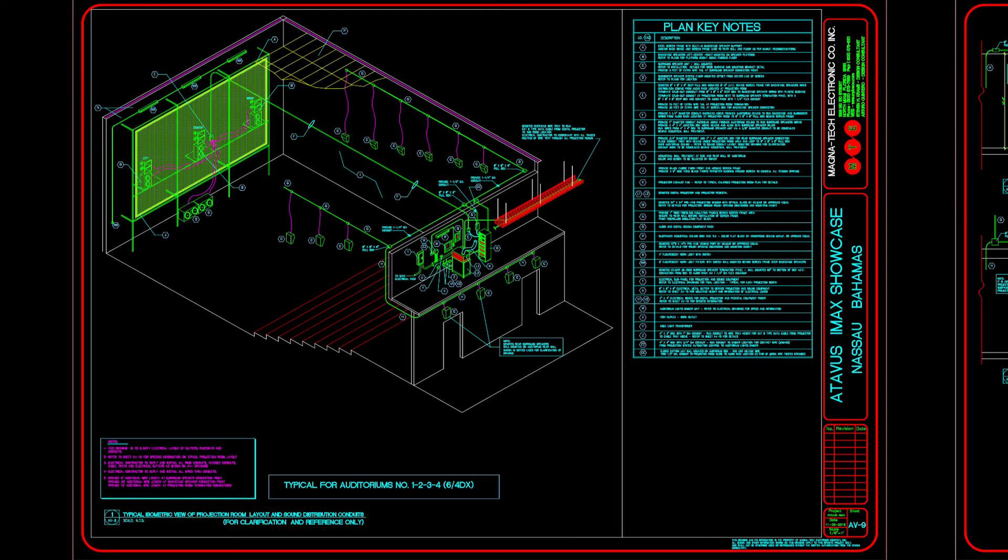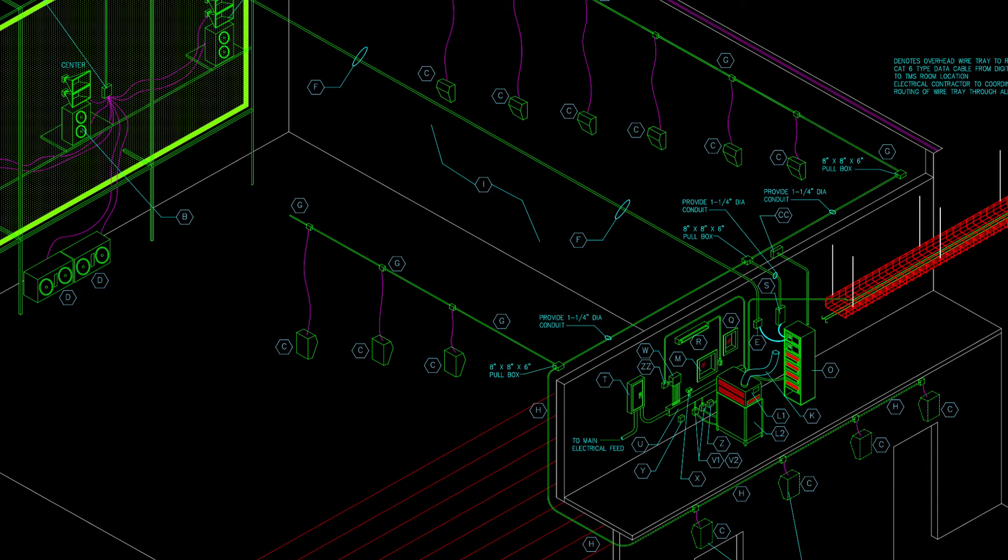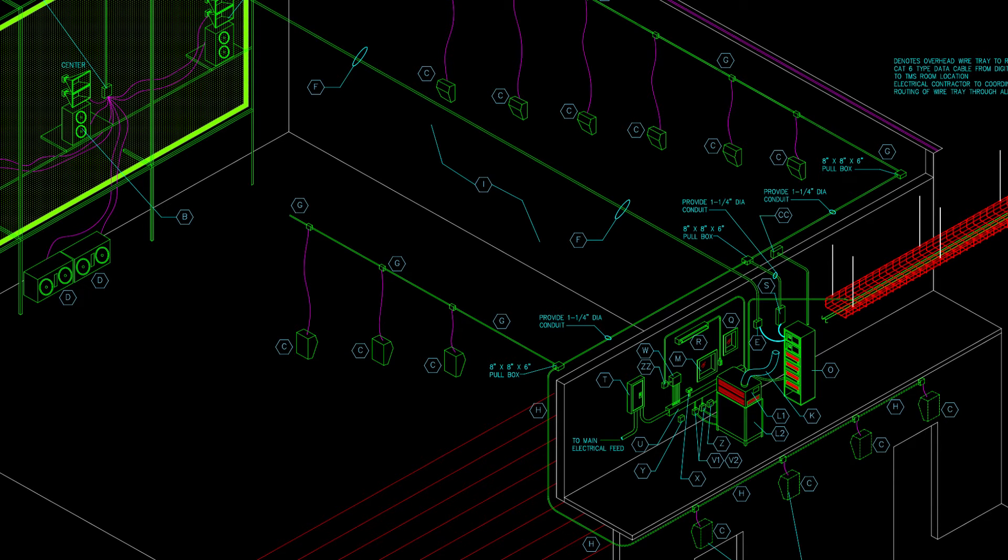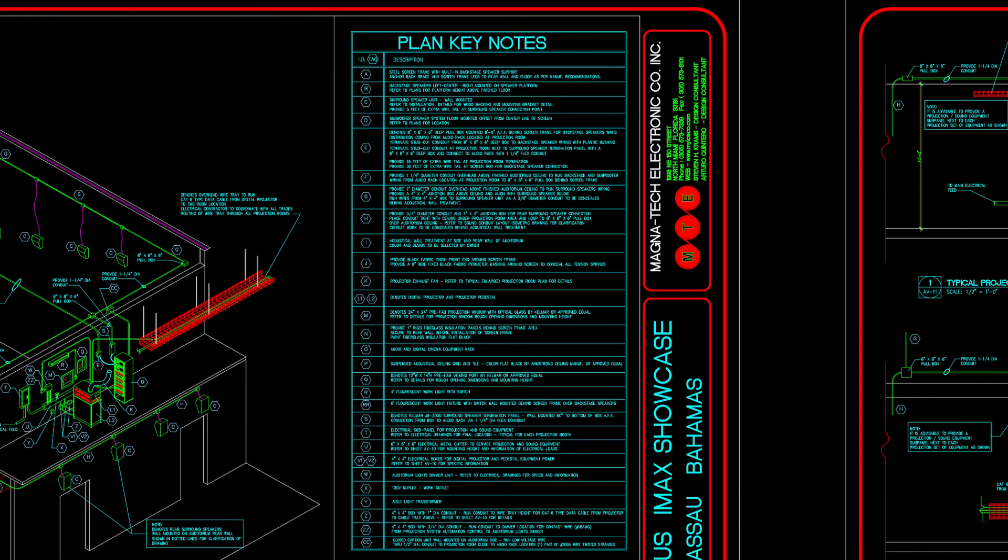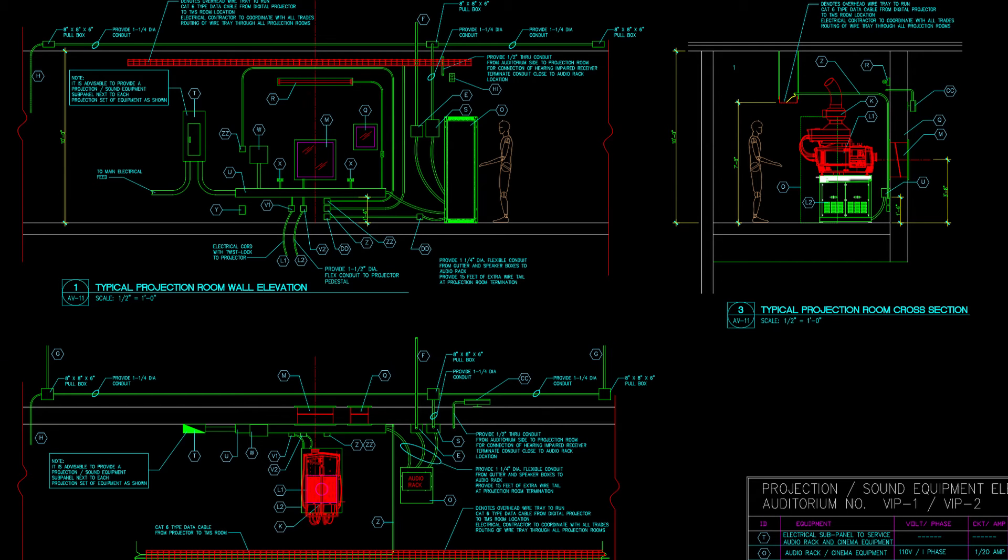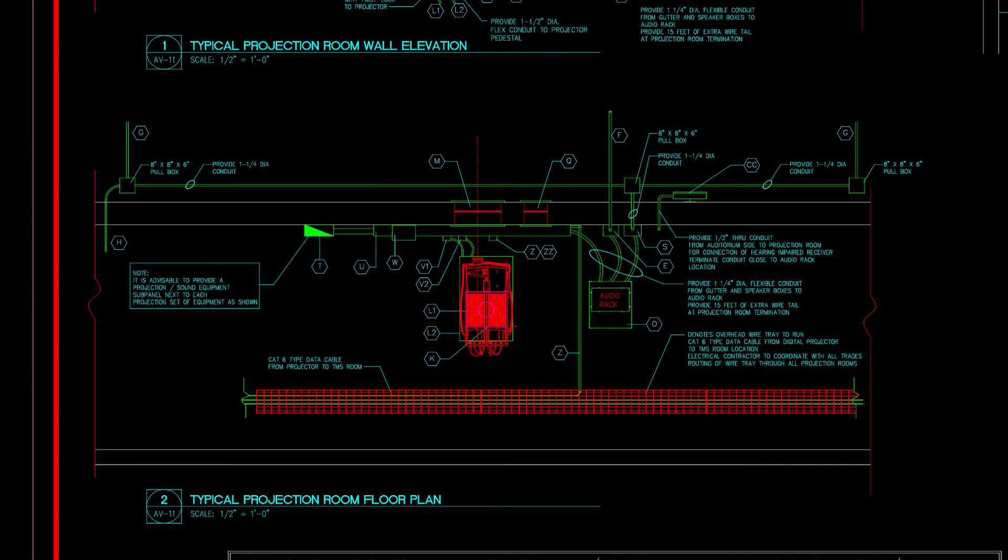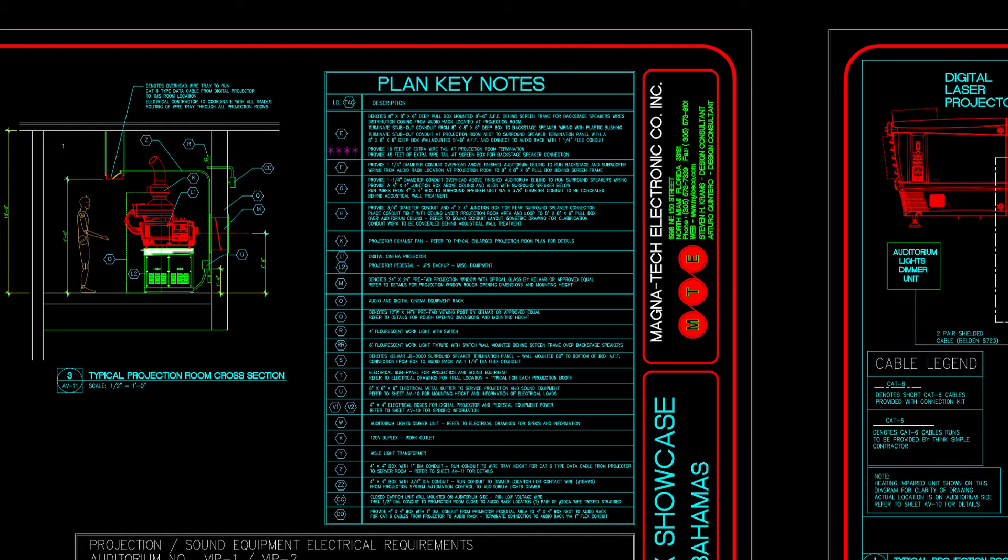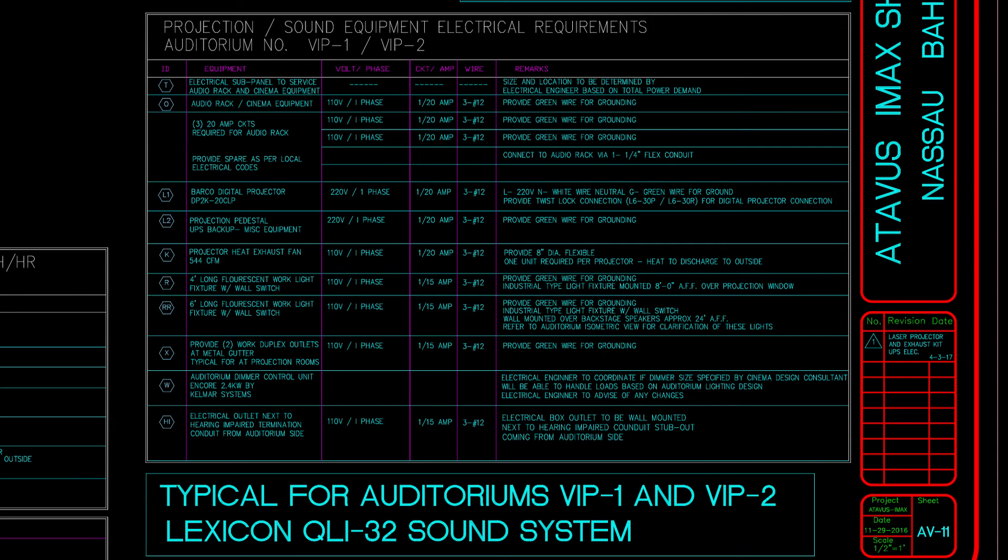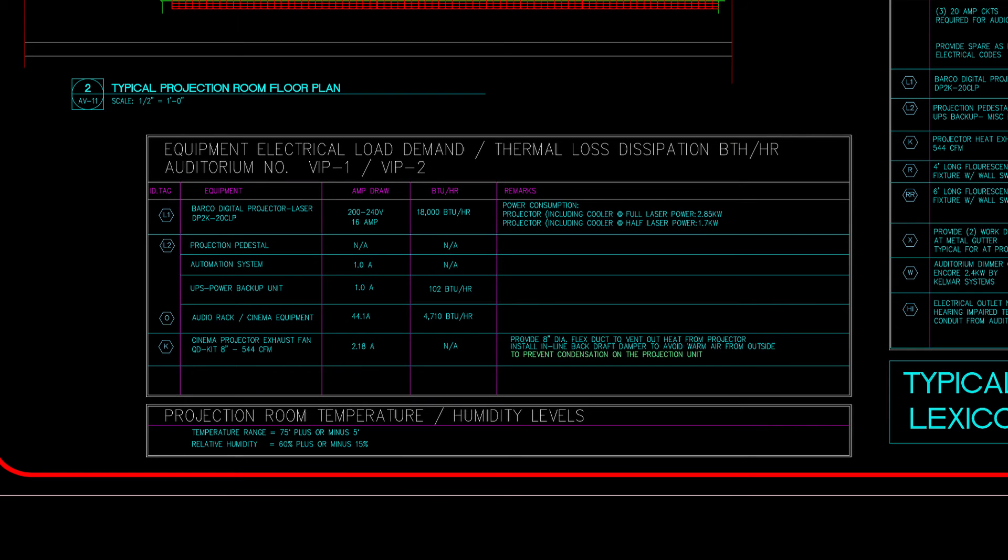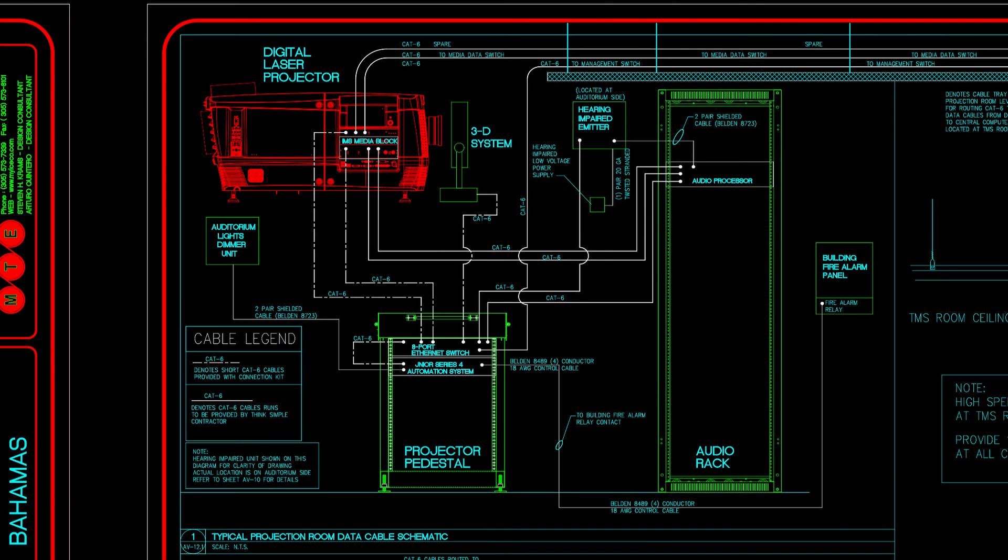Therefore, we developed an isometric view of an auditorium to outline all the required sound wire conduits, diameters, routing, electrical boxes and conduits, all beginning with the notes to specify all the required information needed to complete the project. As part of our technical set of plans, a drawing is developed for each projection room with different views indicating all electrical conduit and boxes, speaker splicing boxes, projector and pedestal, audio rack location and all is keyed into our keynotes for the description of each item. An information panel is provided for the electrical requirements of each component and also thermal loss dissipation, temperature and humidity levels are taken into account.